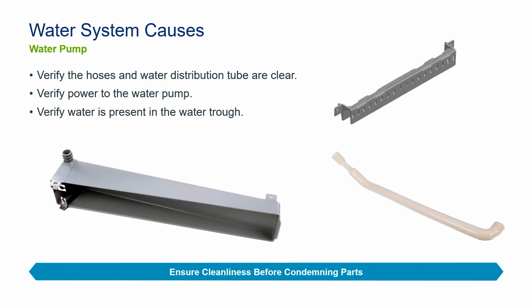The worst look for anybody is finding out, hey, I just put this new part in, and it's still doing the same thing. Hey, look, I pulled off the hose, it's full of calcium, it's full of lime, it's full of whatever's in your water. You clean that all out and now it's working. Well, the old pump might have been working had you done that. We're not sure. Take care of preventative maintenance before ever jumping to corrective maintenance.